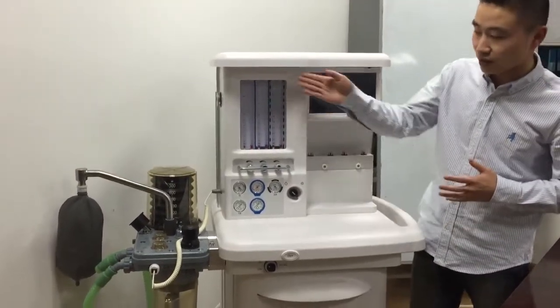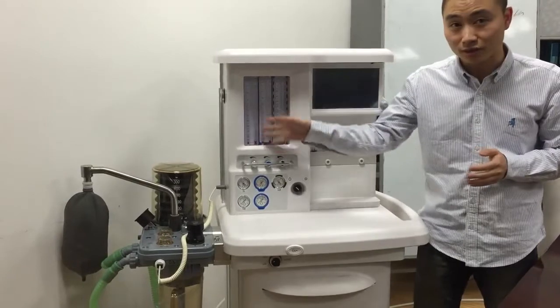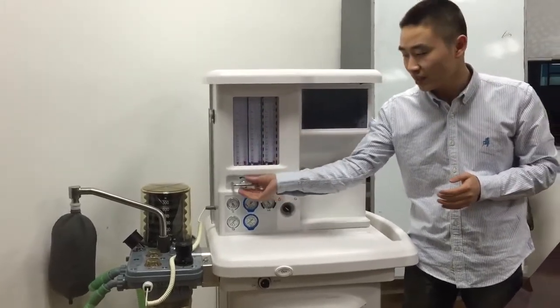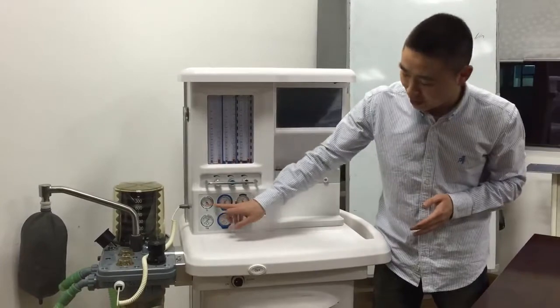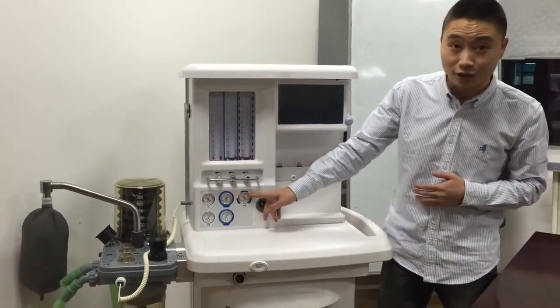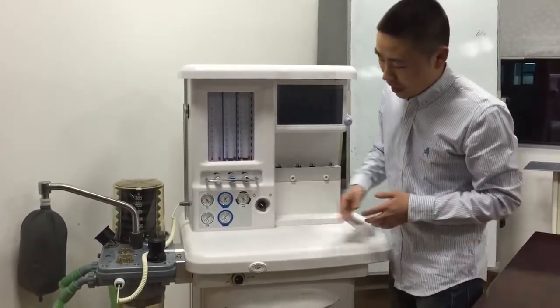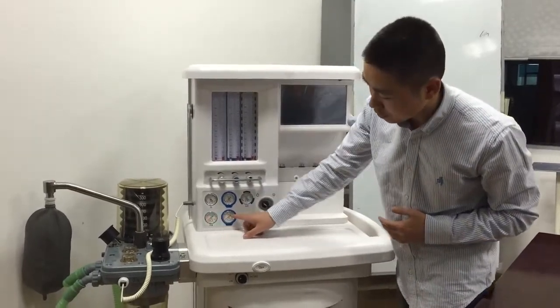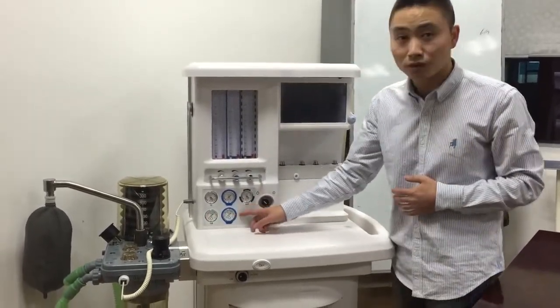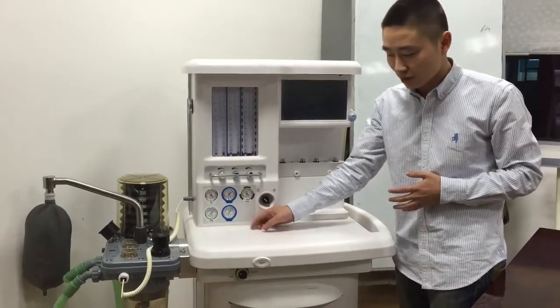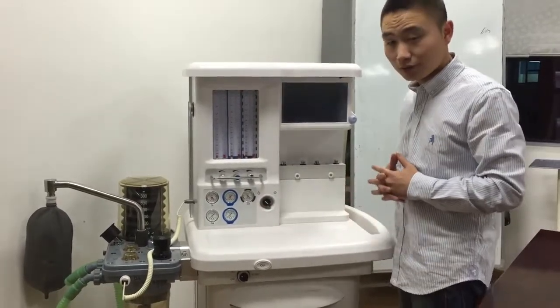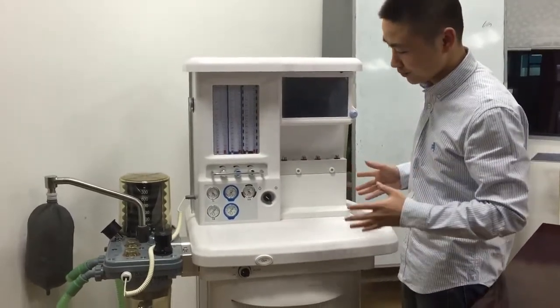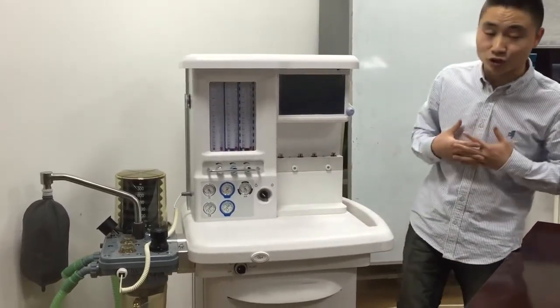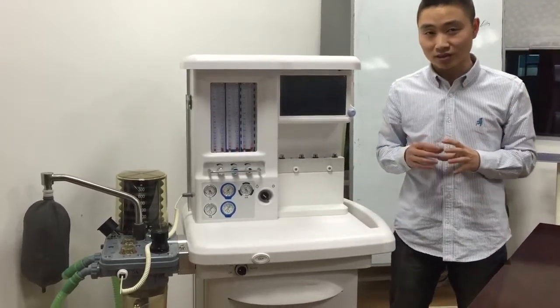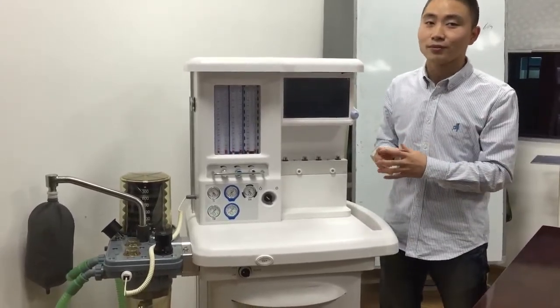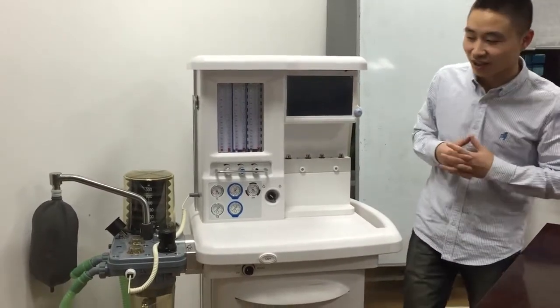We can start from this side, which is the 6 tube flow meter mechanical control, built with 3 gas types: oxygen, air, and nitrous. We also have the yoke system for oxygen and nitrous. But we still have one more space for an optional gas. Maybe it can be oxygen, air, or nitrous, depending on the need. So we're trying to make our anesthesia machine customized, which means you can configure the machine yourself, like you're buying a car.